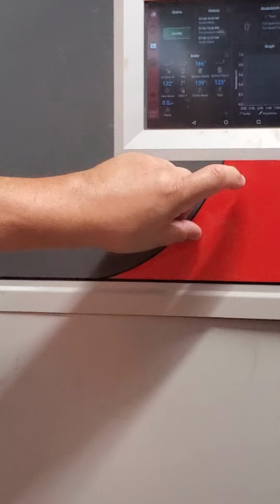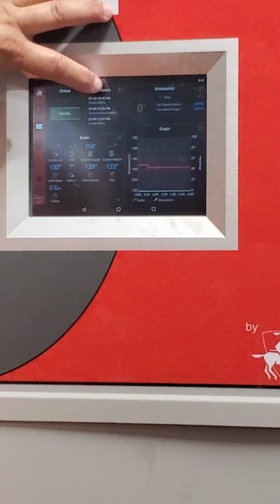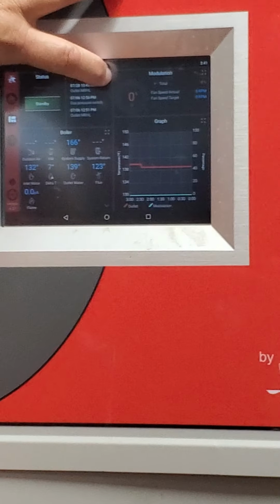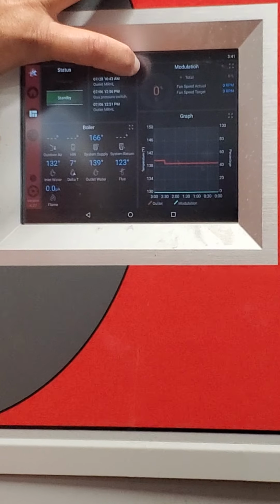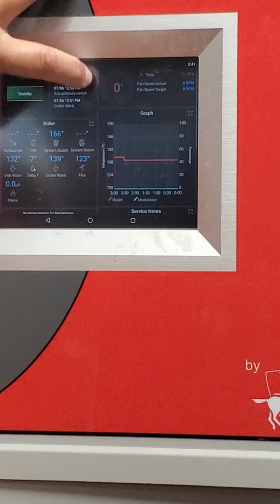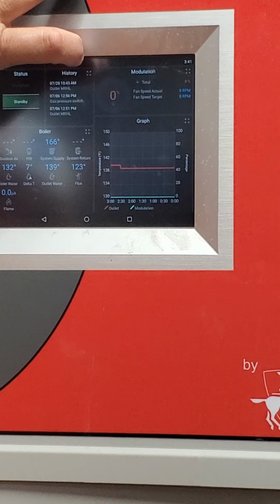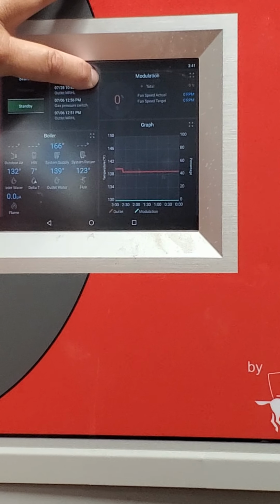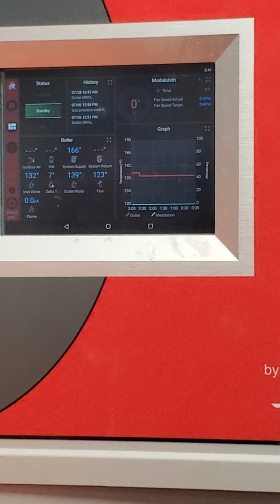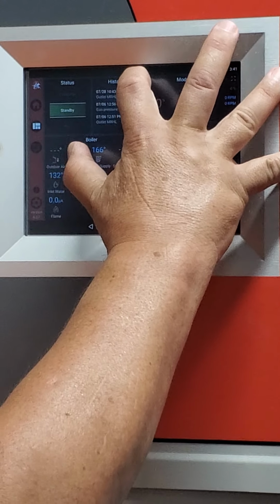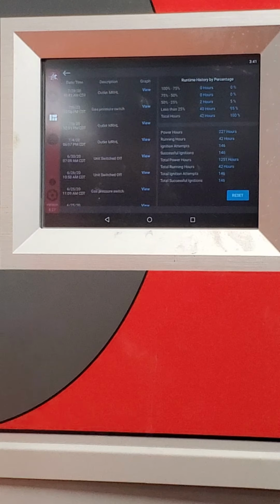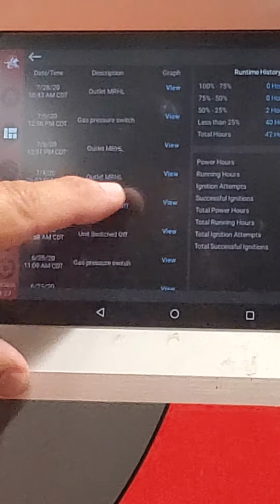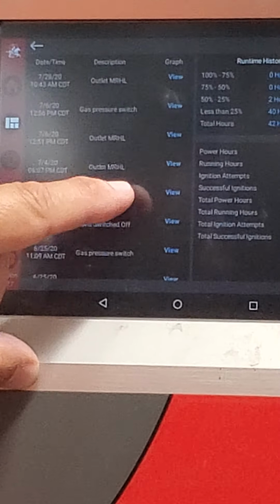You can come into the history screen. It has a little arrow on it as well. You can press that button and it will tell you the history of all the past lockouts. It's a little temperamental. And it'll tell you manual reset high limit, gas pressure switch, outlet manual reset high limit.